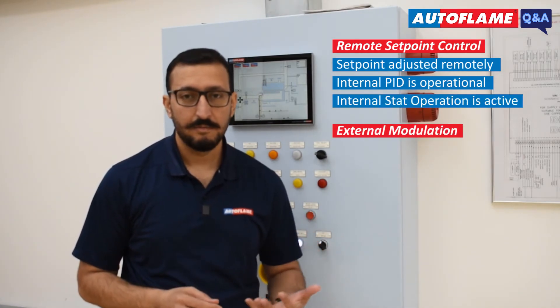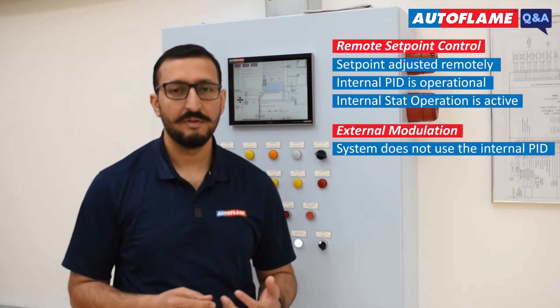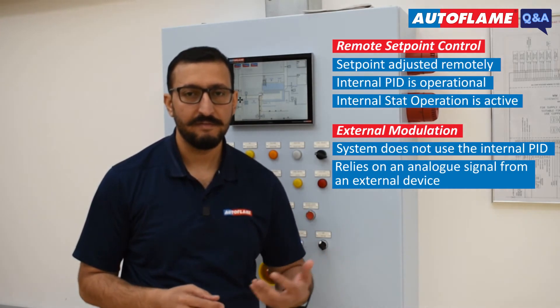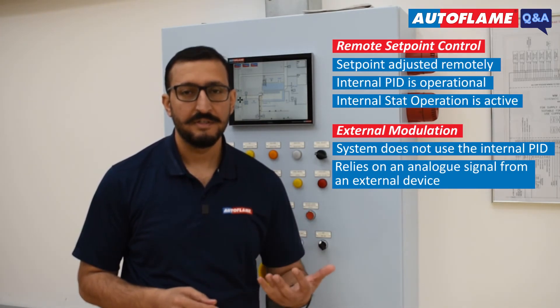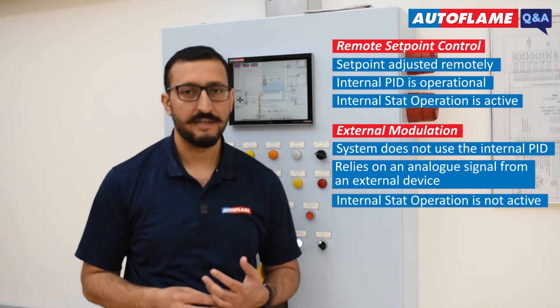In external modulation, the system does not use the internal PID. It solely relies on the analog signal received from the external device to adjust its firing rate, and the system does not have the internal stat operation active.